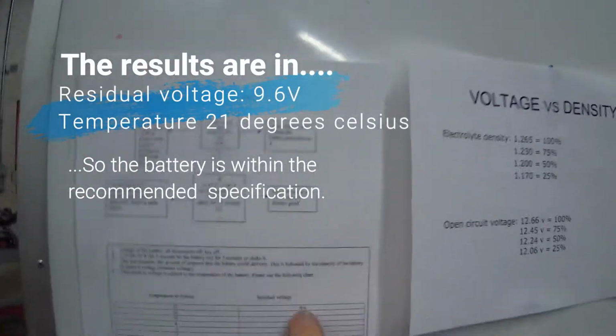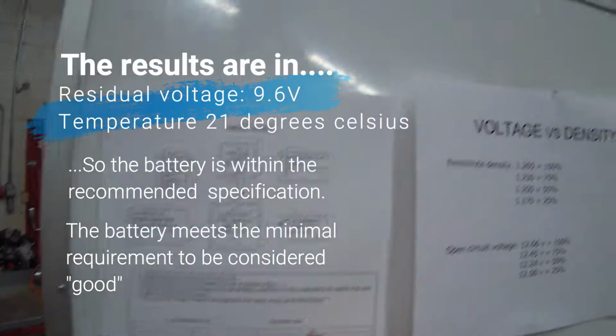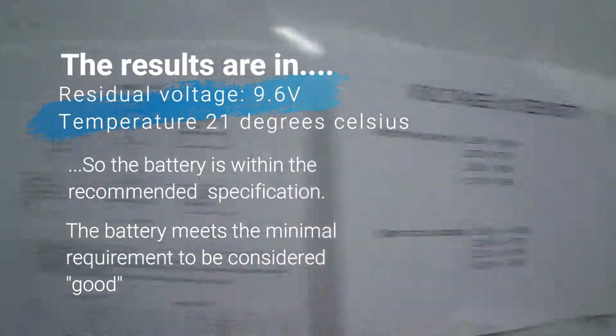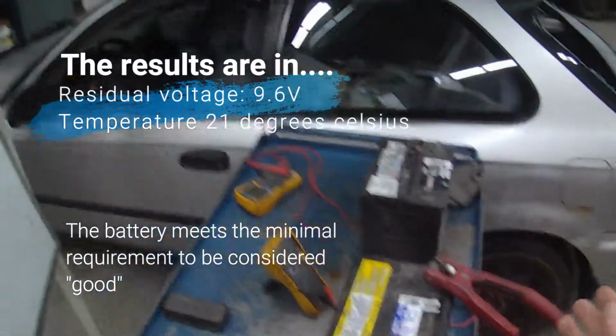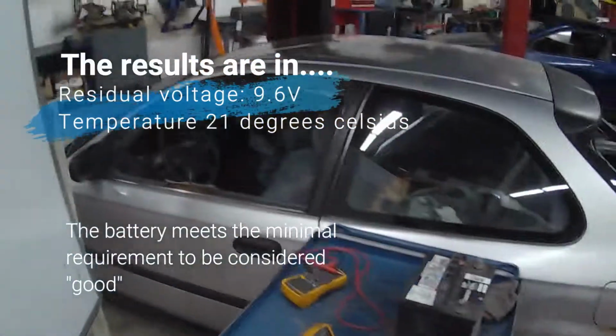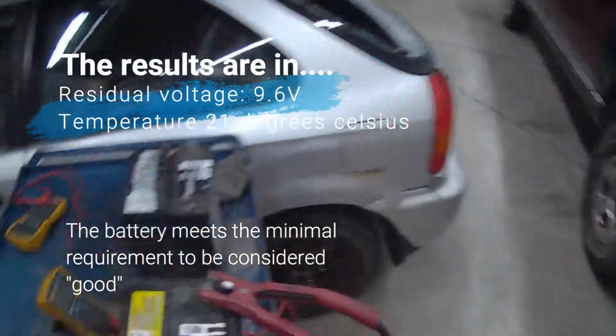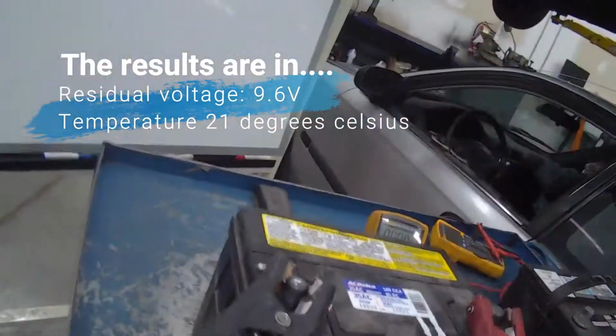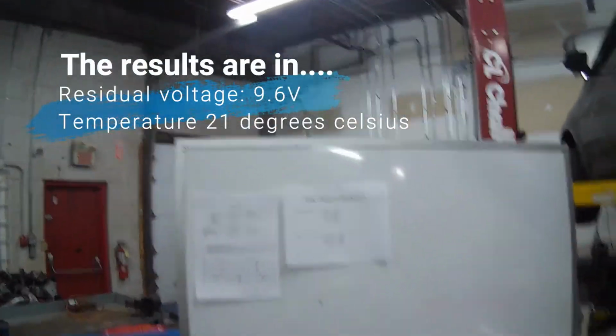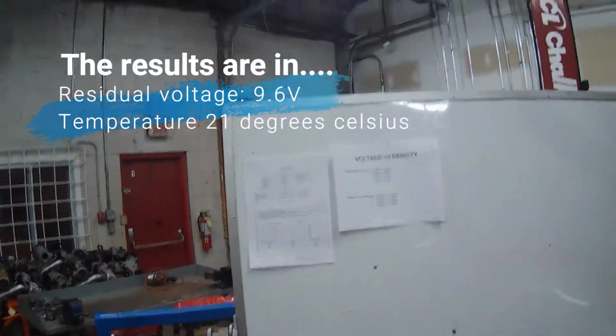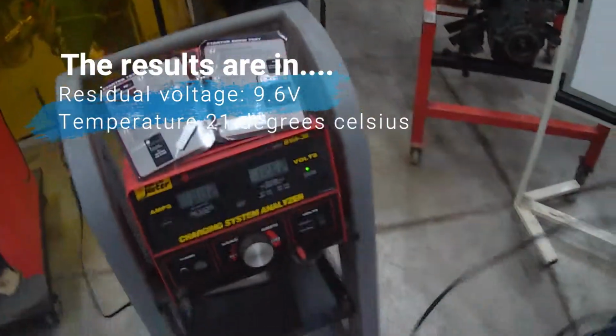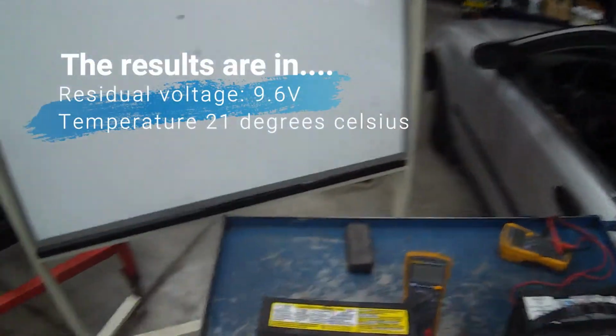What I would suggest to the customer is to say, look, you're at the minimum residual voltage. A little lower than that and I'd have to say the battery is not good. So I'll declare the battery good, but suggest you'll probably have to change it in a few months, especially if it's very cold. But honestly, from a technical point, I have to say that battery is good - good means residual voltage of 9.6 or higher at room temperature.